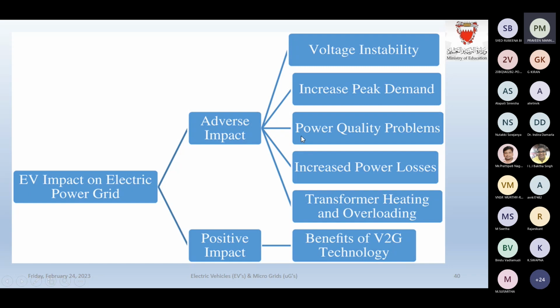We are using converter technologies, and in these there is a possibility of harmonics. When harmonics are developed and introduced into the system, this affects the distribution transformer and other power system components due to overheating. When this happens, the lifetime of these devices reduces, instead of 20 years it comes to roughly 10 years.